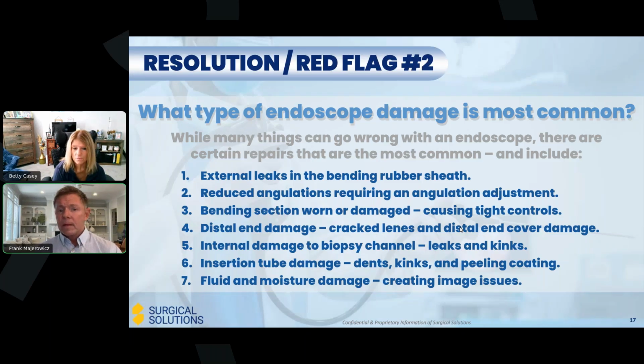Reduced angulations, that's where the angulation control knobs are loose. They may be too loose, they may be too tight. These types of issues, in some cases, can be normal wear and tear that are unavoidable. They just get loose over time and they need to come back in routinely for annual adjustments. And in other cases, it could be something that is preventable. Perhaps the scope is being over-torqued, or not coming out for enough routine maintenance, causing them to get overly tight. So that's another very common cause for endoscopes coming in for repair. Worn bending sections, again, causing tight control knobs.